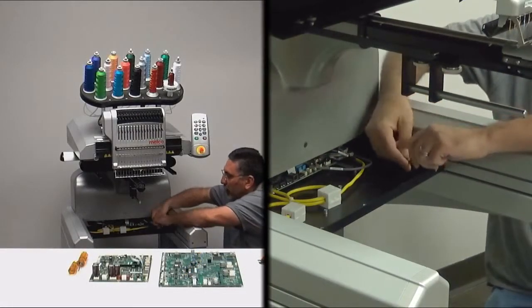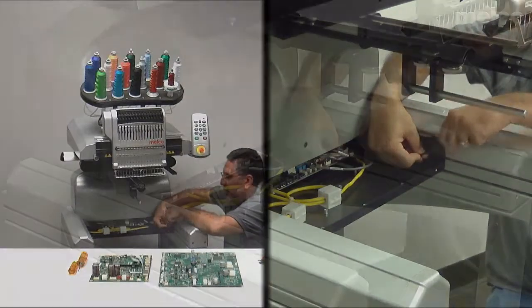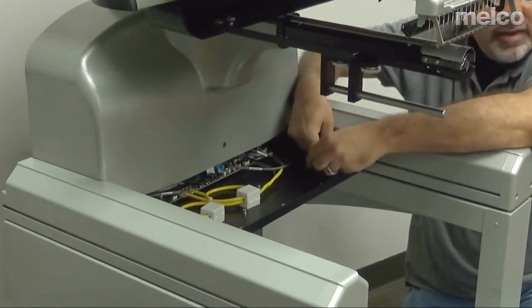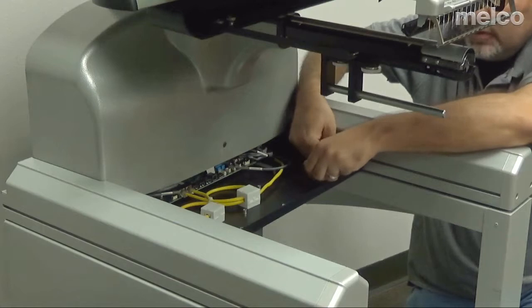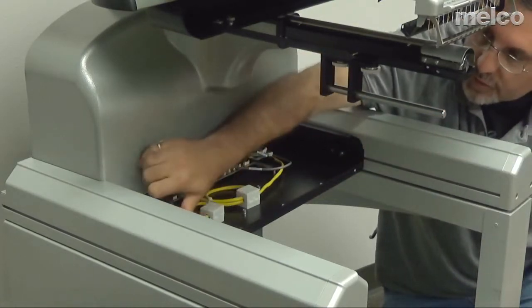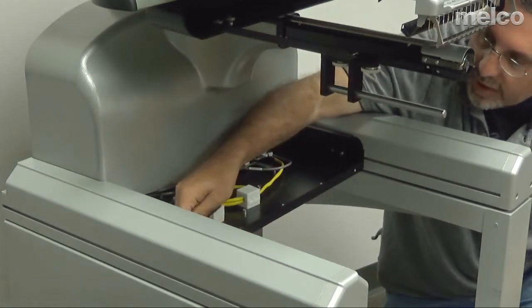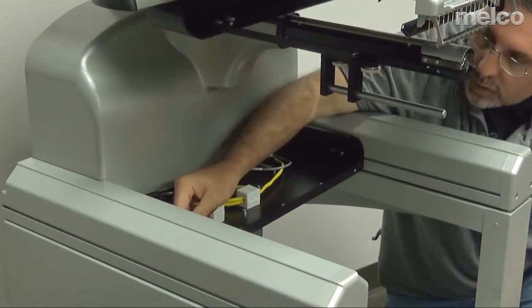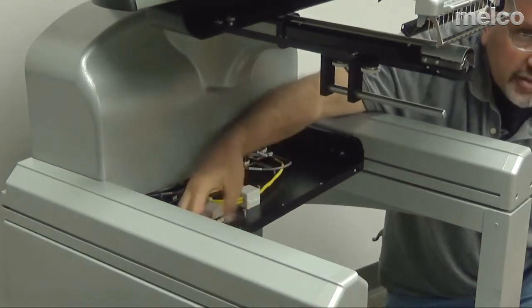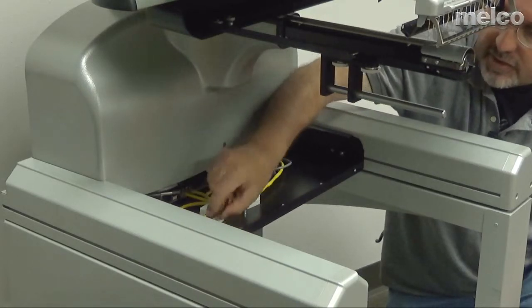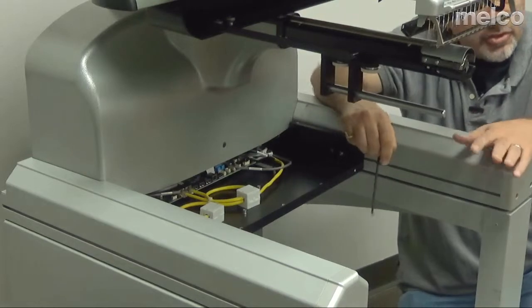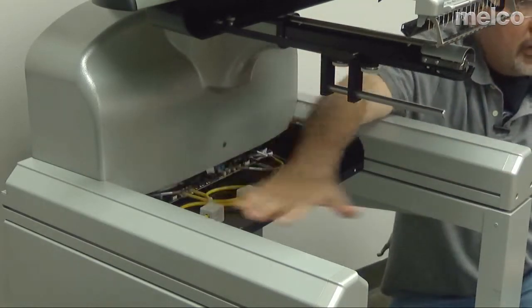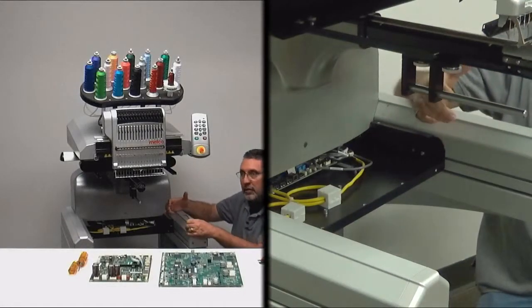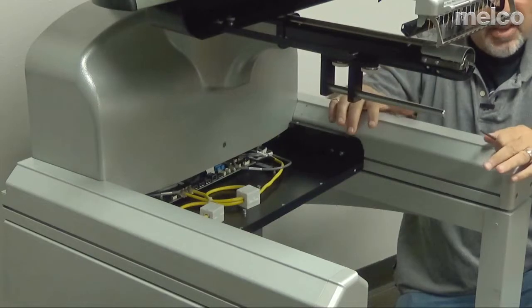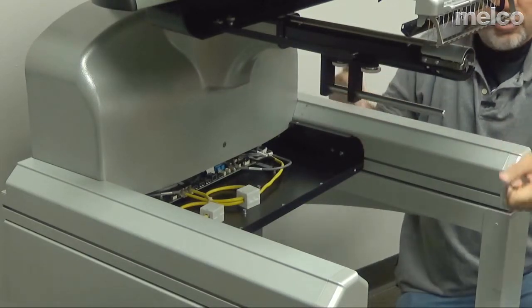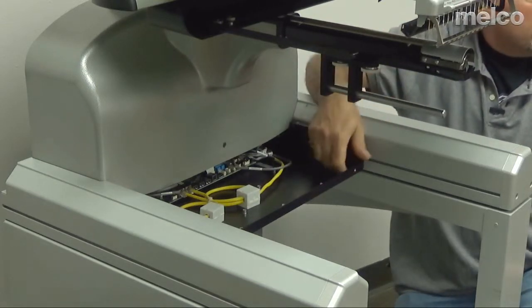Once we have this cover removed, on the right and left side of this black tray, there are 2 4 millimeter locking bolts. Now these bolts are on sliders, so they do not need to be completely removed. They need to just be loosened up so that we can slide this black tray forward. Now, if you are working on an Amaya XT, an Amaya XTS, an XT Bravo, XTS Bravo, or just a Bravo in general, over this area right here, you have that big plastic base cover. That base cover is not attached to the machine by hardware. You can just lift that cover off and then you will have access to the main board.